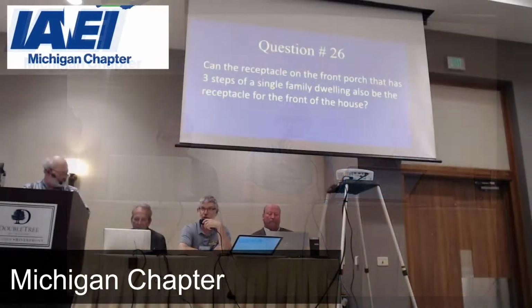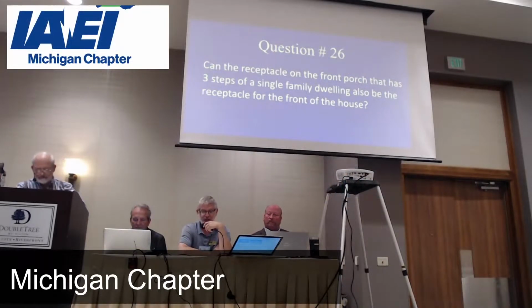The code requires that not less than 1 receptacle outlet that is readily accessible from grade level and not located more than 6.5 feet above grade shall be installed front and back of each dwelling unit with direct access to grade. That's a wording change. It used to be it had to be accessible at grade level. Now it's accessible from grade level. And as long as that receptacle on that porch that is only 3 steps up is less than 6.5 feet high from that grade, it'll meet that requirement. E3901.7 or 210.52(E)(1).